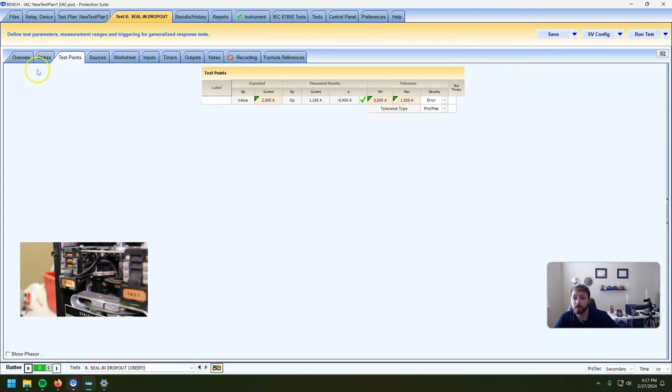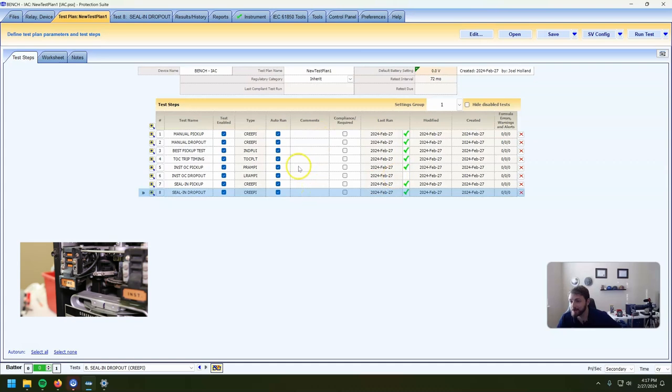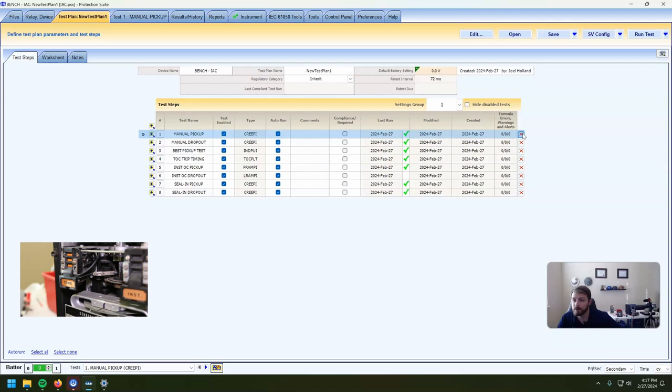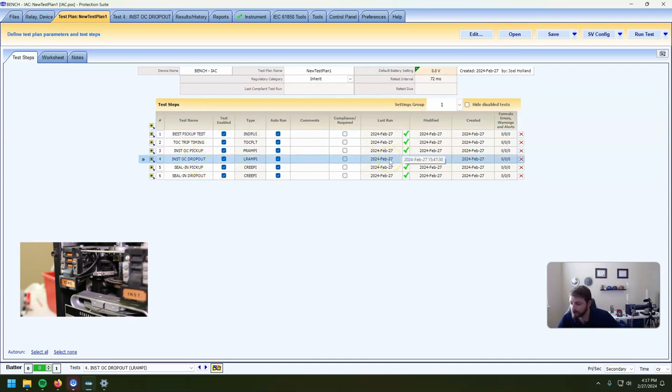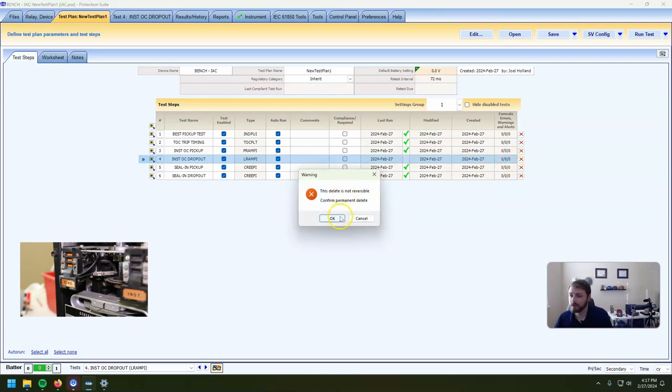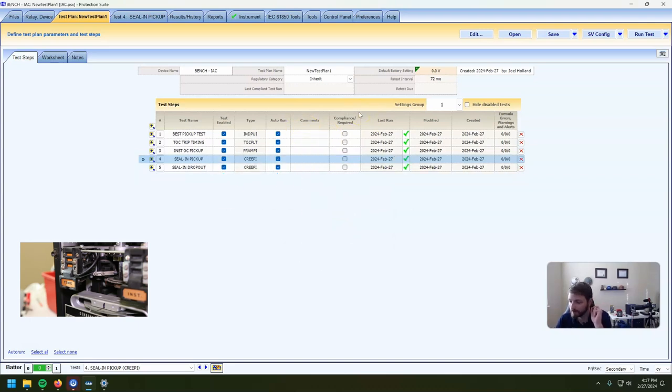We tested the heck out of this relay — that was way more than we actually needed to do. The manual pickup, the manual dropout, and the instantaneous OC dropout tests aren't strictly necessary. Realistically, if you're doing these out in the field and you get good results on the inductive pickup, the TOC timing, and the instantaneous pickup, the relay works. This potentially 100-year-old relay is in very, very good shape. That's it for the GE IAC relay. If you've watched all of these videos, you should have a fairly good grasp on what to do if you see one out in the field. Leave any questions down in the comments — like, share, subscribe. Thanks guys.